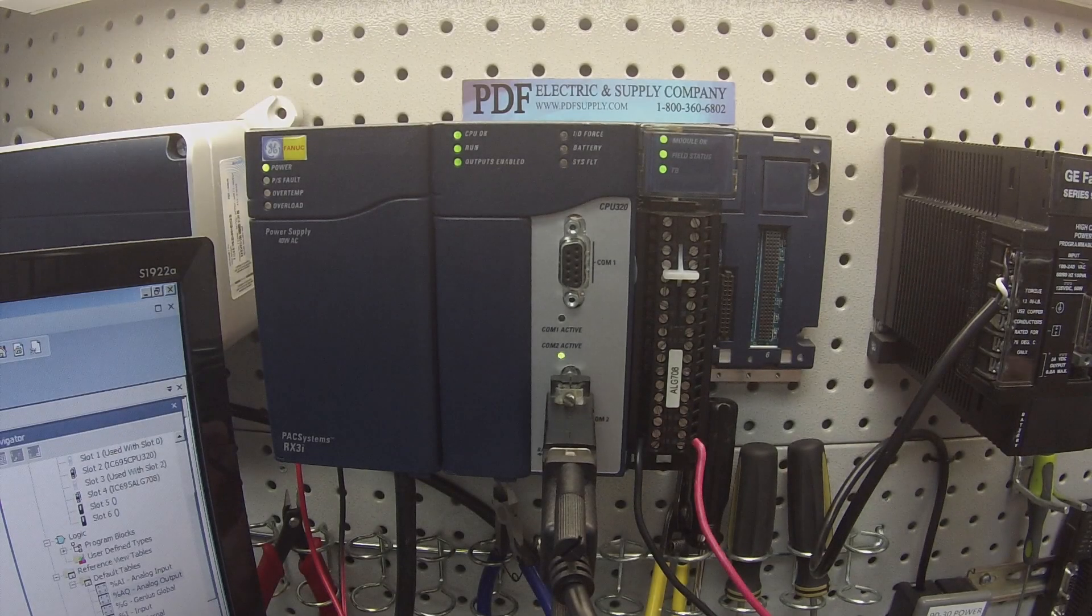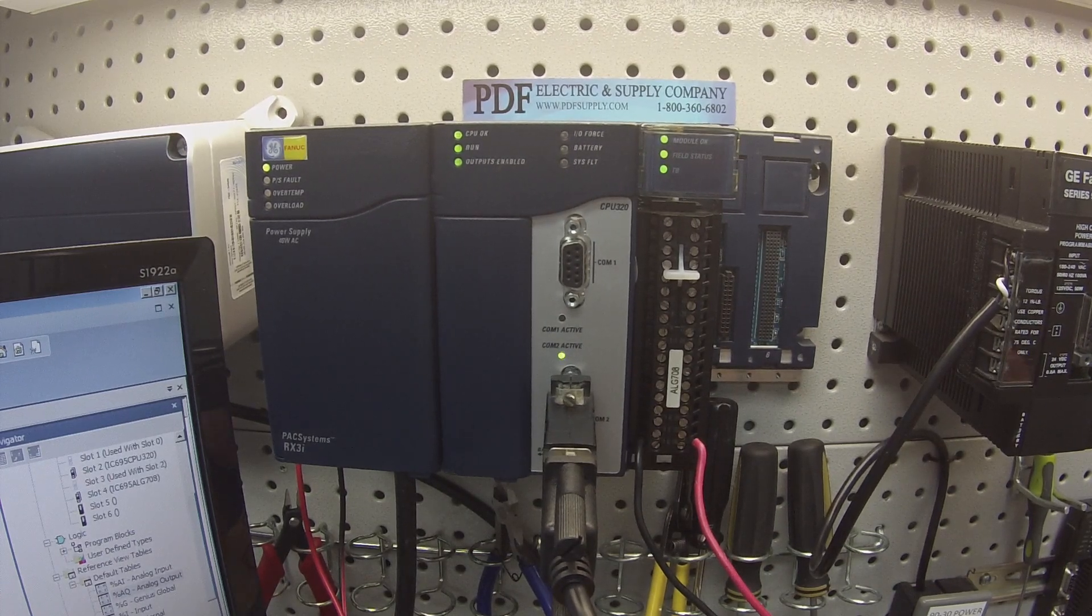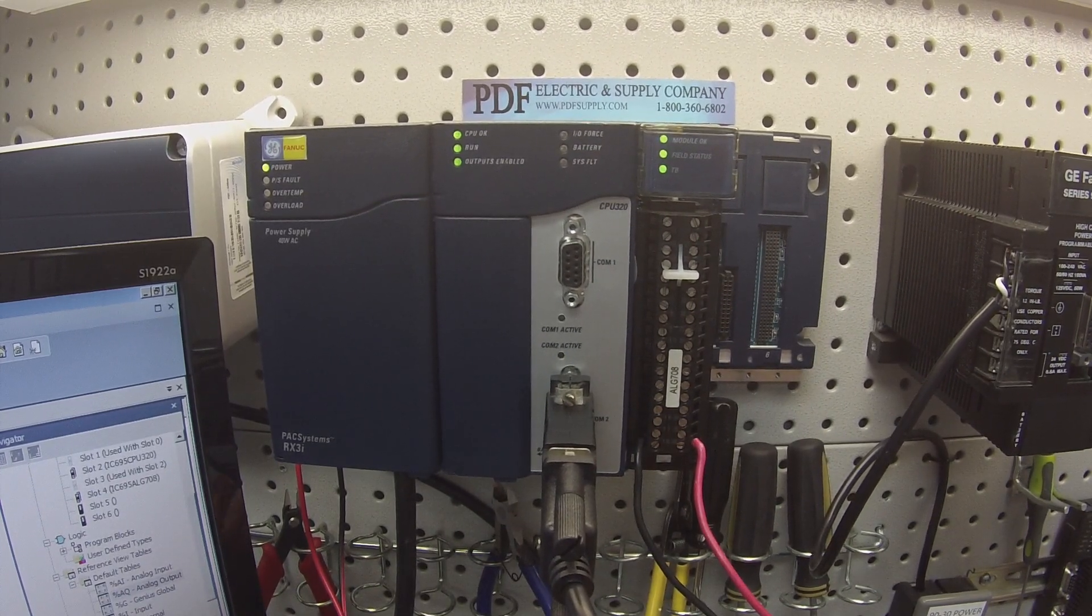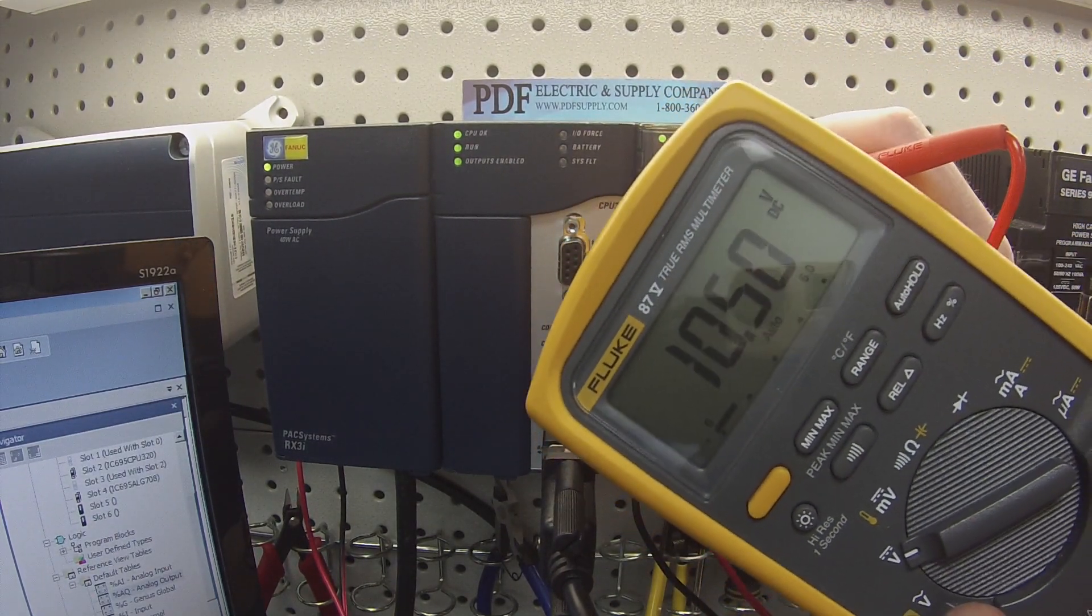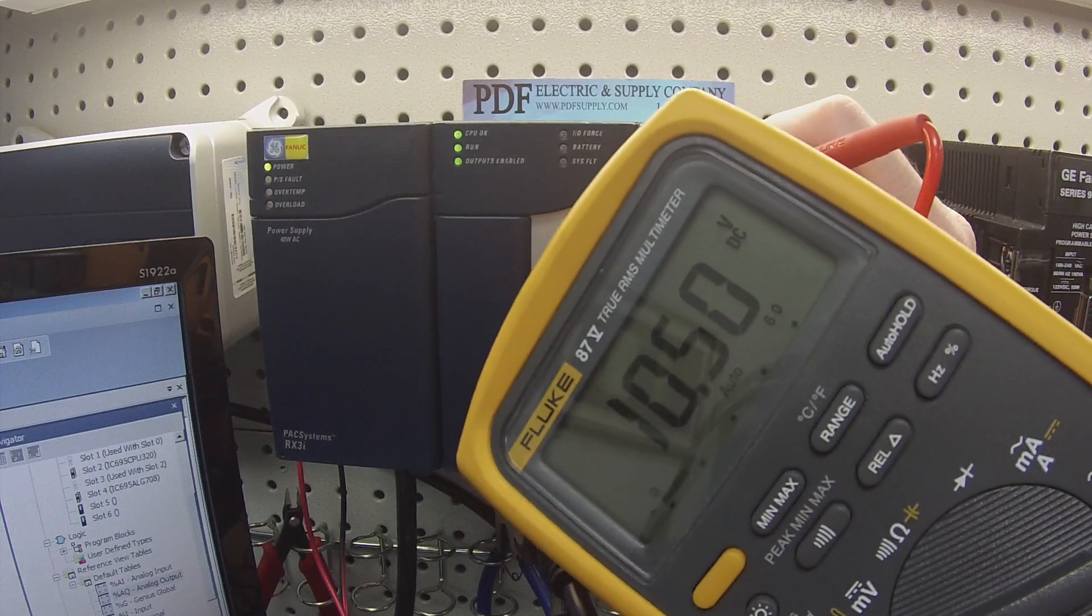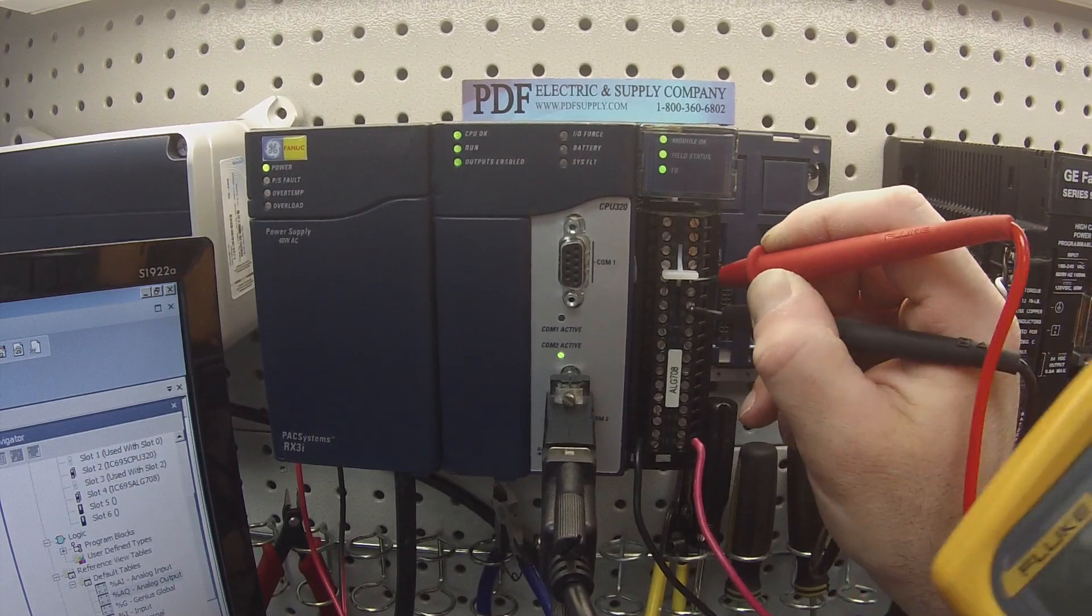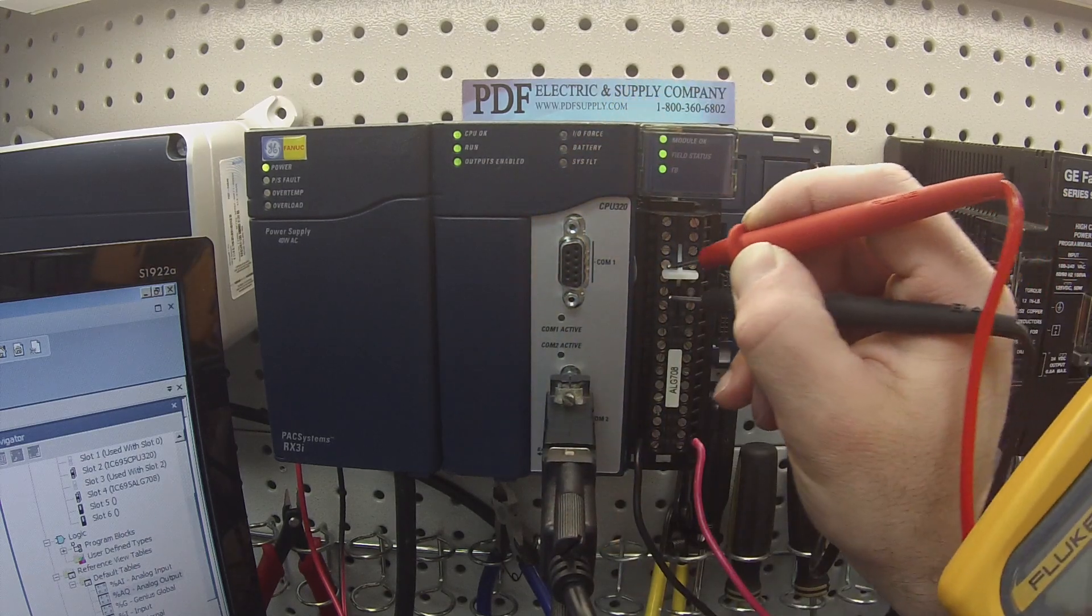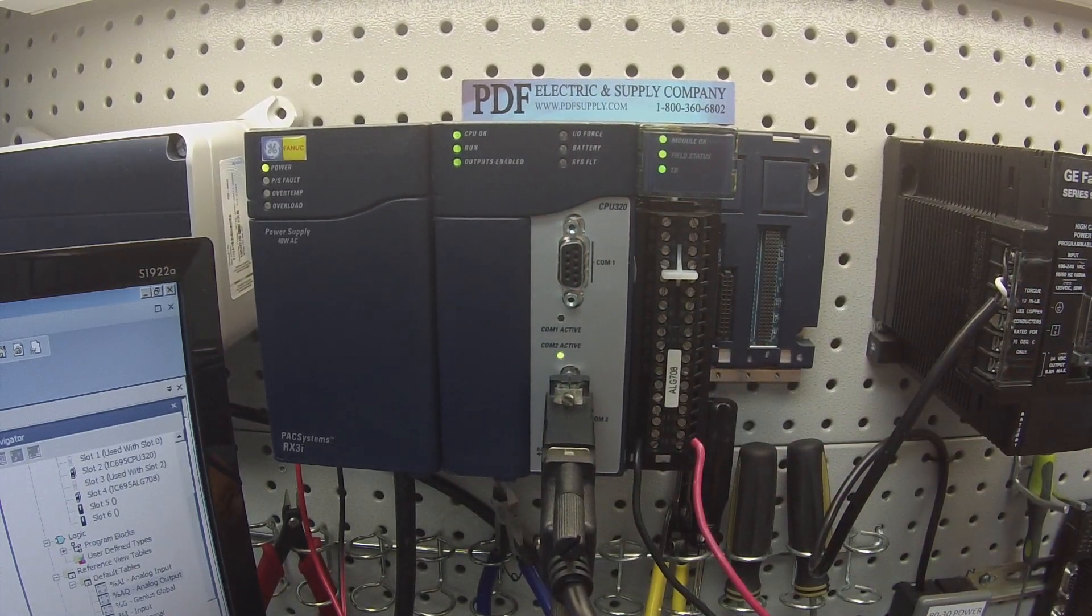If you take quick note to my multimeter, what I'm going to do is the probes that relate to the terminal that I was just discussing. For example, on channel 1, this is 19 and 21, and we're going to skip 20. If you look on my multimeter, I'm getting 10.5 volts DC. That's good. We got the full 10 volts. I get another channel, same exact voltage. It's stable. It's not moving up or down. It's a solid 10.5 volts, channel 3, channel 4, and so on. You can keep testing these in that manner.